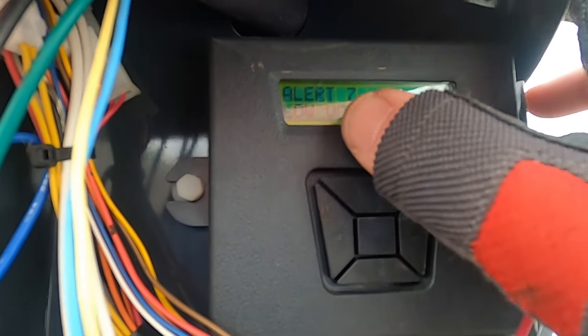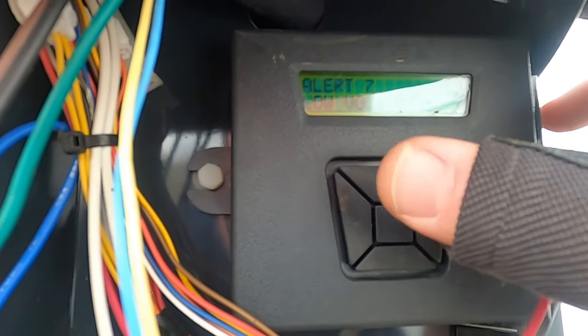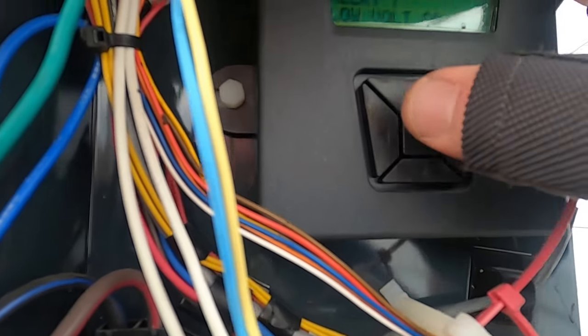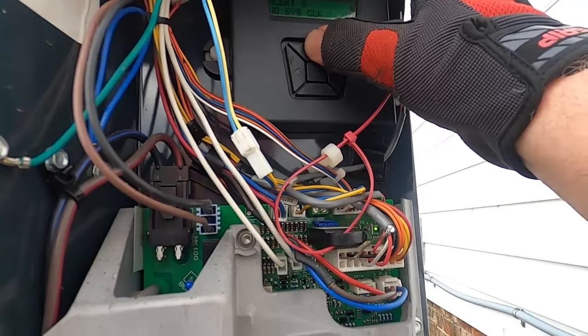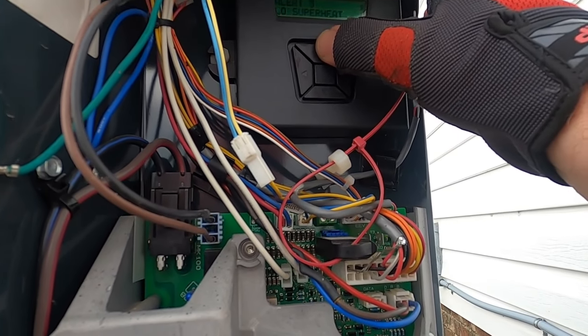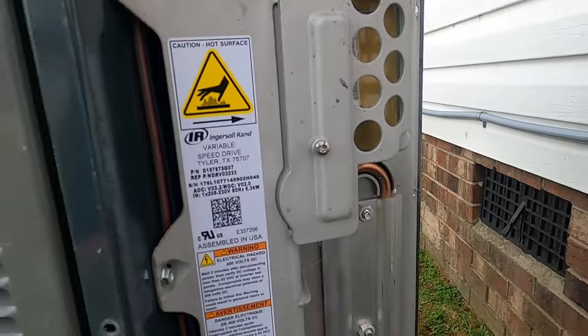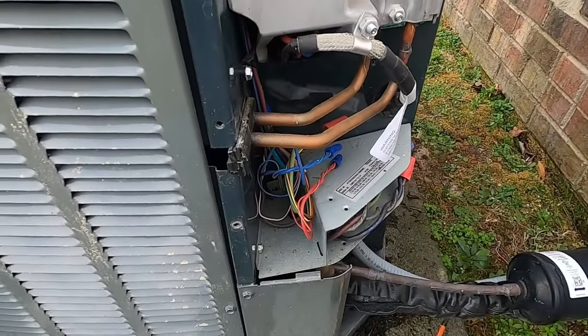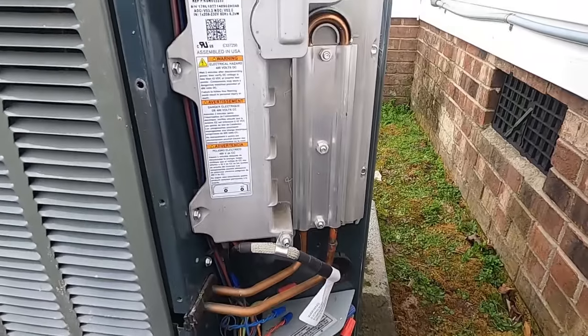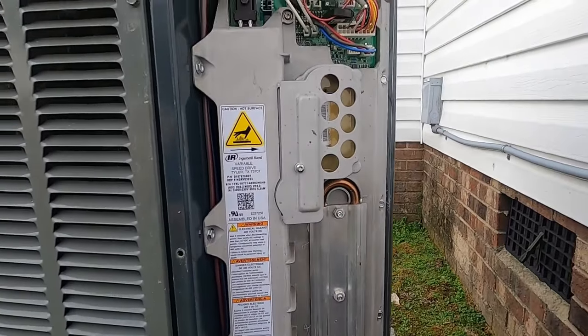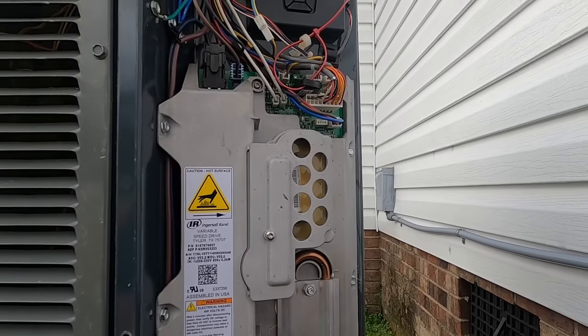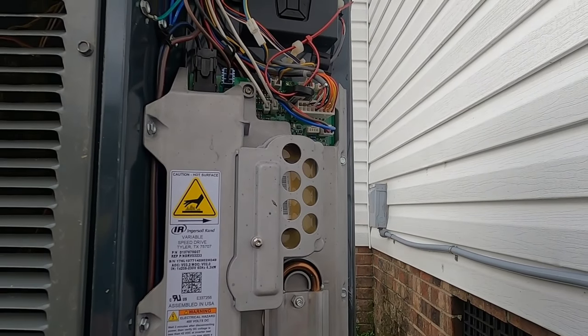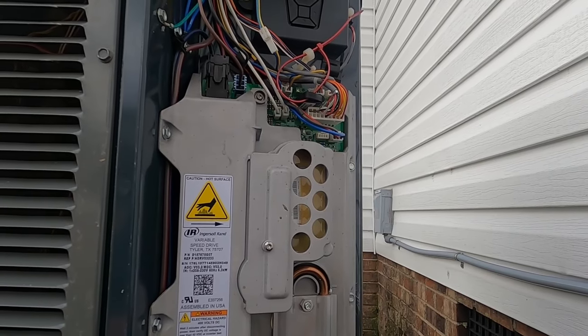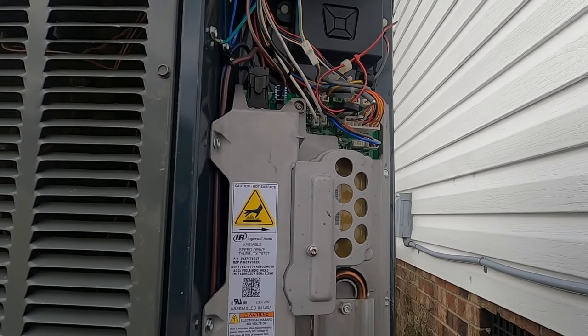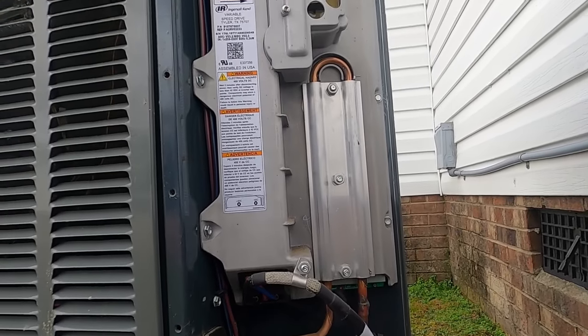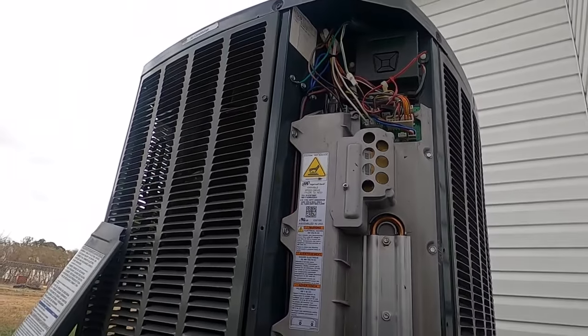And then the DC low volt, you'll see that if you turn off the power to it, which we would have done while we were doing the maintenance. You'll see that fault. So I'm just going to turn it on and run it. I'm going to check the air handler, see if there are any red light flashes under the house, and just do a once over on it. But there's nothing in the alert history that tells me that anything happened to this unit yesterday. Because if it shuts down for whatever reason, it's going to flash an alert for whatever went wrong with it. So let me check it out. Let's go into the house and see if we get an alert code.